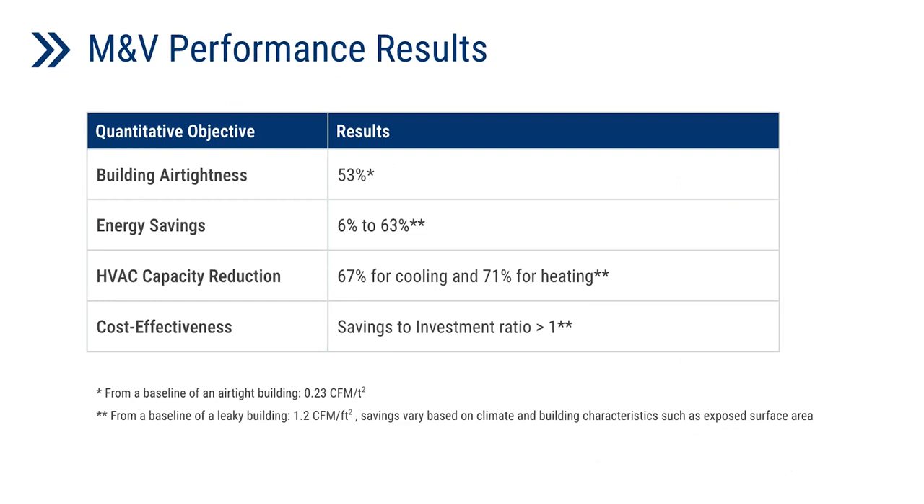This table shows the major outcomes of our M&V performance results. The building airtightness through our demonstration increased by 53% — it was initially 0.23 CFM per square foot at 75 Pascals, and was lowered to 0.11 CFM per square foot. Energy modeling shows savings of 6 to 63% on energy use. Regarding HVAC capacity reduction, a maximum of 67% reduction for cooling and 71% reduction for heating is achieved for buildings with a leaky baseline located in cold climates and with a large exposed surface area. The savings-to-investment ratio exceeded 1 for specific buildings.